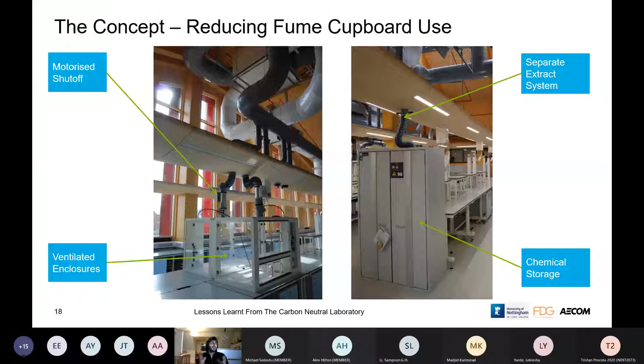We still needed the fume cupboards because they're an absolutely critical part for the science and for keeping the scientists safe, but we designed them to be as low energy as possible. Like I was saying before, we provided a separate ventilation system for each lab to make sure it was as low energy as possible, with the supply and extract requirements exactly matched to each lab. There's something called a low face velocity to the fume cupboards, so they're designed to require as little airflow as possible through them to keep the scientists safe.